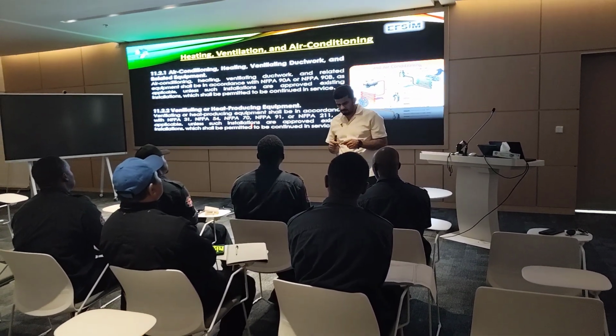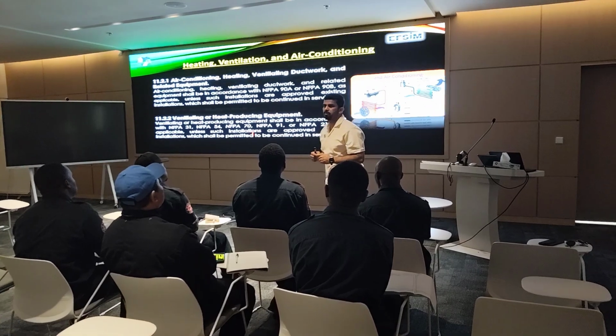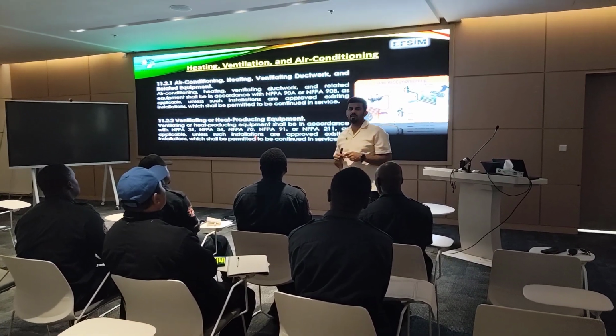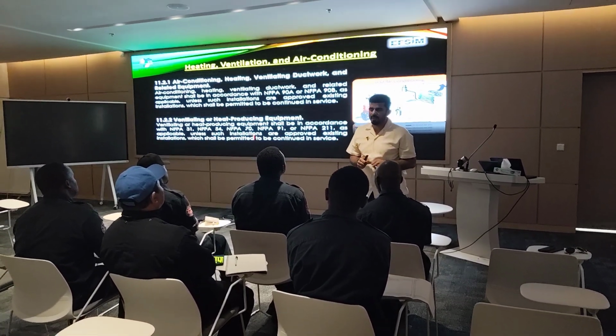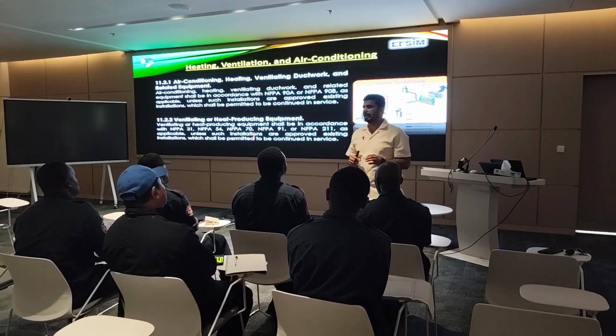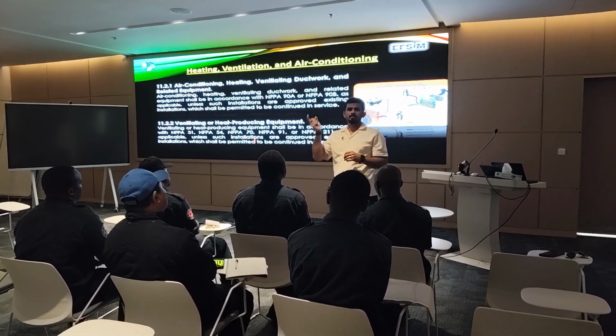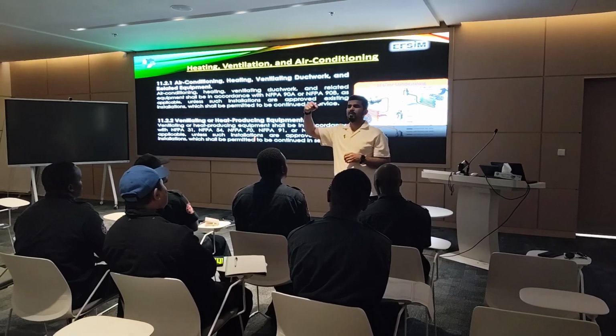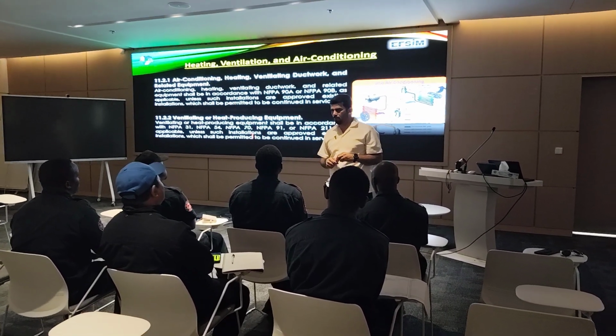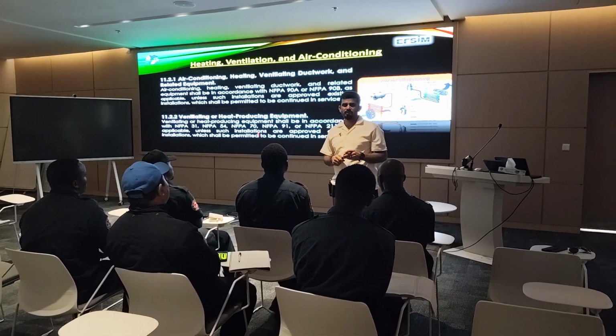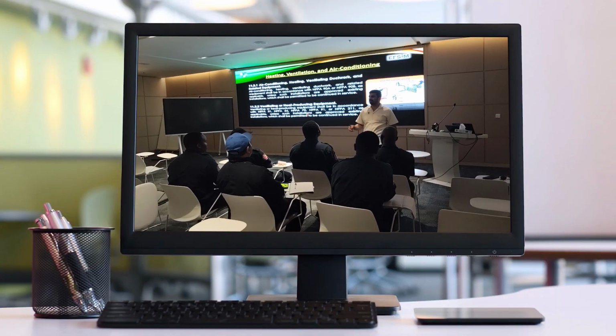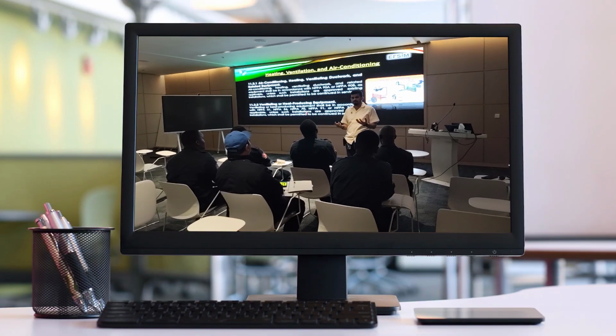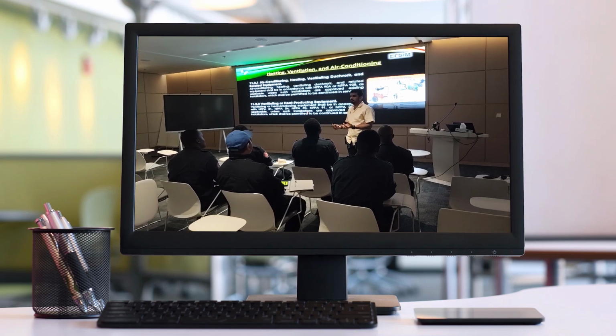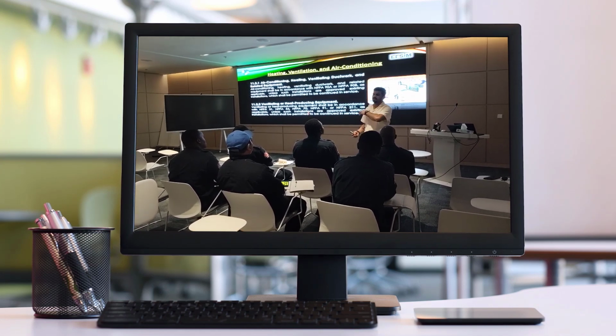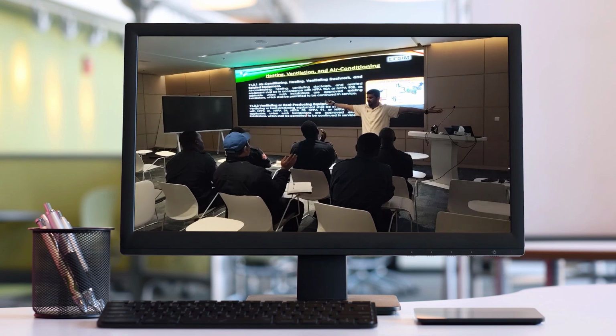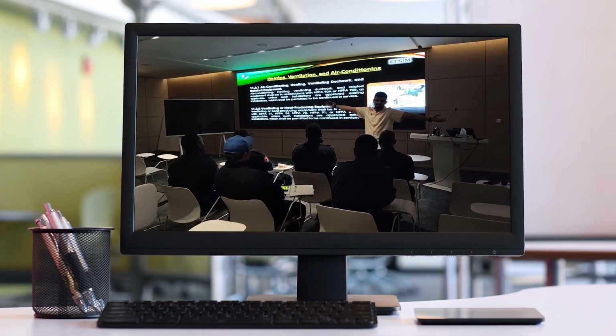Okay. So, what is the main issue in this kind of system? In case of emergency, if you cannot stop the HVAC system, that smoke will go through on all areas. How? Chief, because again, we have a ducting system. Yeah. Okay. So if the smoke goes in one duct, it means it's going to spread on all areas.